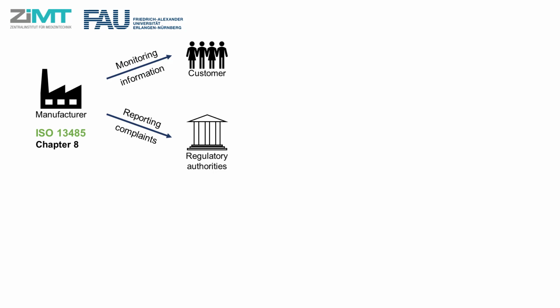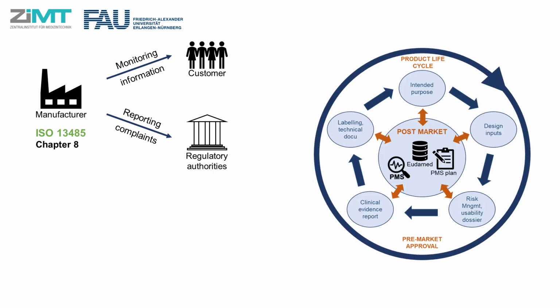Post-market surveillance shall be an integral part of the product's life cycle from the development to market in a continuous way focused on cycles of product safety improvement. During the early stage of development of a medical device, post-market surveillance should be considered. For example, how to collect information from the device on the market, and how the service team shall support the customer and generate reports must be considered as inputs for the design of a product.